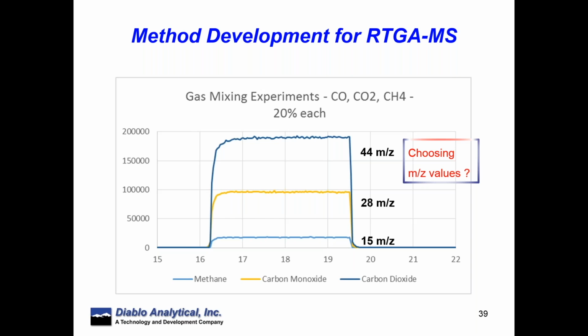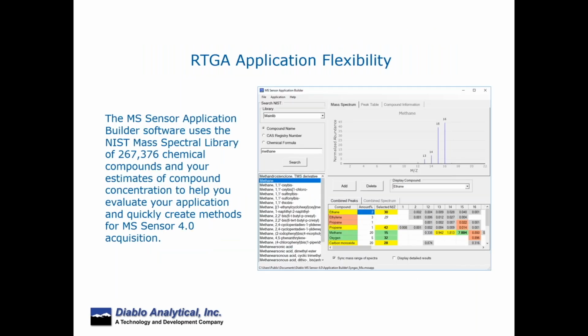So let's look at method development. How did we decide which mass to charge values to choose? So, we could say, well, here we've got carbon monoxide, CO2, and methane, and we're going to use 44, 28, and 15. But how did we come up with those? Those are each ions corresponding, but how did we pick those particular ions? Okay, so we have something called the application builder. And it's based on the NIST library.